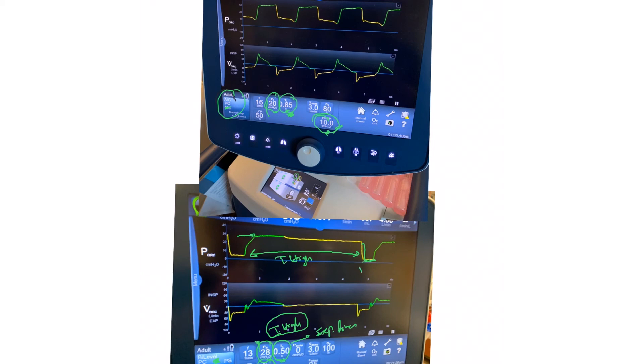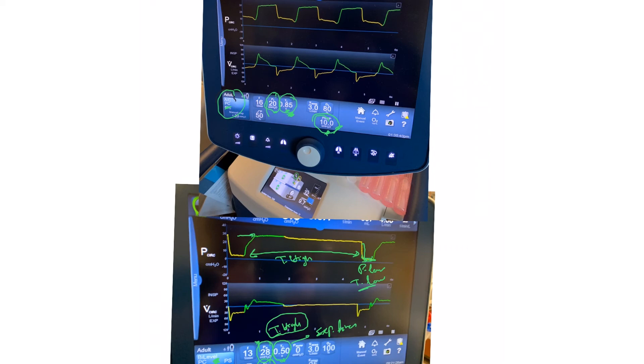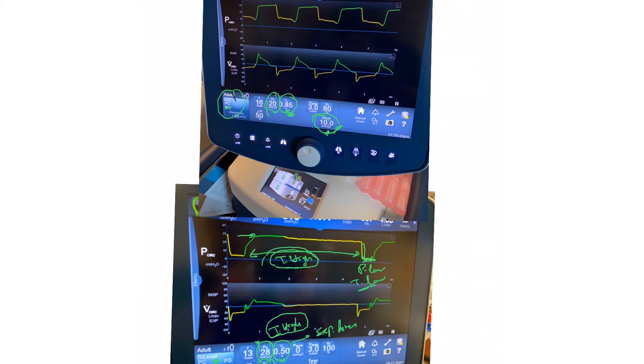This is the P low, and here we make it zero. You can make it zero, you can make it five. The P low will continue for the time T low, and then the cycle repeats itself. That's what we call airway pressure release ventilation. We keep a continuous positive pressure for a specific period of time. So we keep a continuous positive pressure, we call it P high, for a specific period of time called T high. And this correlates to the inspiratory pressure and inspiratory time in the traditional pressure control mode.